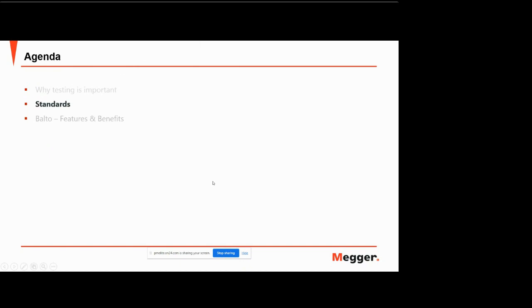Okay, so that's the main reason why we need to do testing. There are also international standards that specify routine maintenance for DC high-speed circuit breakers, and that's what I'll cover in the next section. So this is under the IEC, which is the international standard. We have two standards. The first one I'll talk about is for traction power substations.